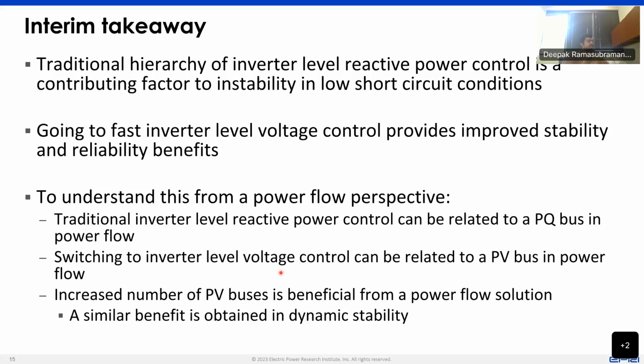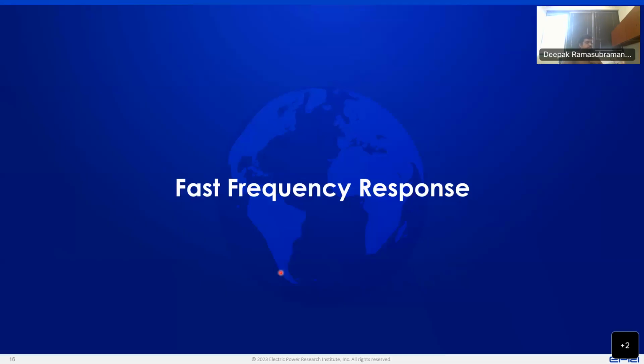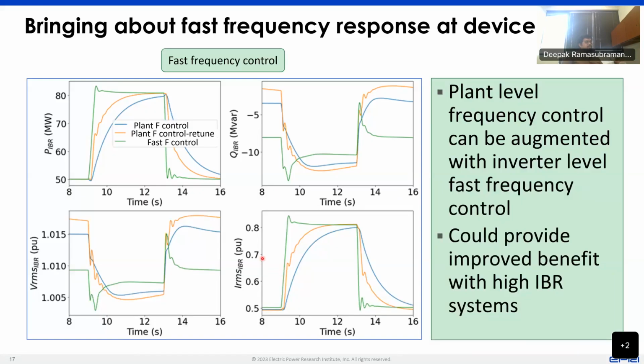So the same concept can be applied in a dynamic stability realm: as you have more of this faster voltage control at the inverter level, you can get an improved reliability benefit. The same concept can be applied to frequency response also. So we have a similar set of curves here, wherein the blue curve is your conventional IBR that has plant level frequency control. There is a little bit of tuning that can be done with the plant level frequency control.